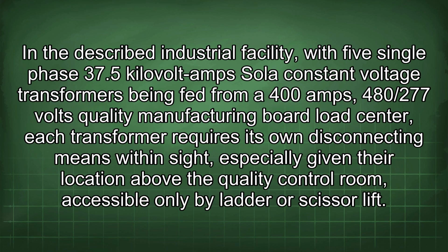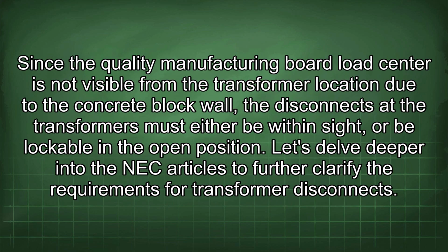In the described industrial facility, with 5 single-phase 37.5 kVA constant voltage transformers being fed from a 400 amp, 480/277 volt quality manufacturing board load center, each transformer requires its own disconnecting means within sight, especially given their location above the quality control room, accessible only by ladder or scissor lift. Since the quality manufacturing board load center is not visible from the transformer location due to the concrete block wall, the disconnects at the transformers must either be within sight or be lockable in the open position.